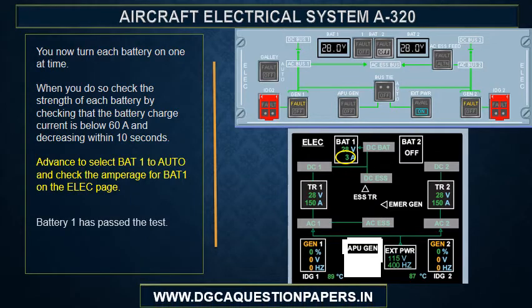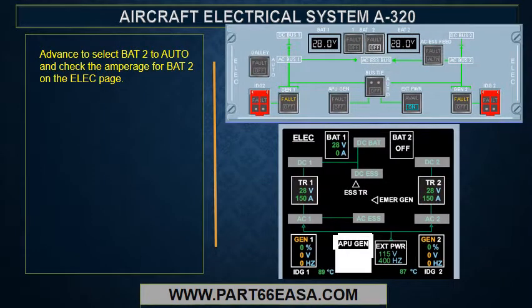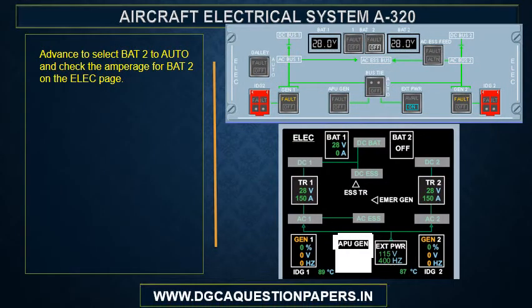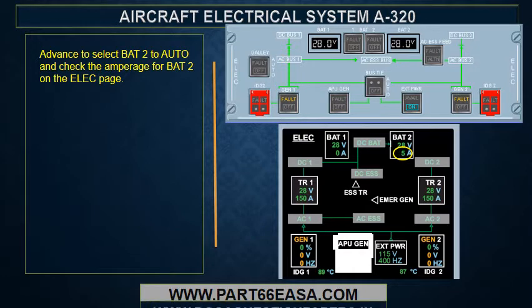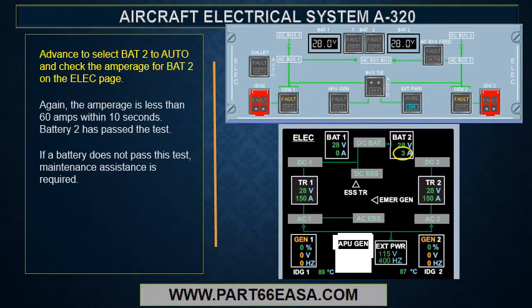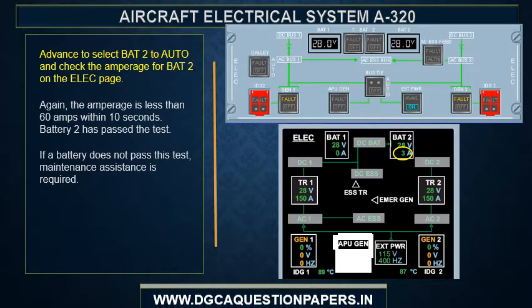Battery 1 has passed the test. Advance to select Battery 2 to auto and check the amperage for Battery 2 on the electrical page. Again, the amperage is less than 60 amps within 10 seconds. Battery 2 has passed the test. If a battery does not pass this test, maintenance assistance is required.